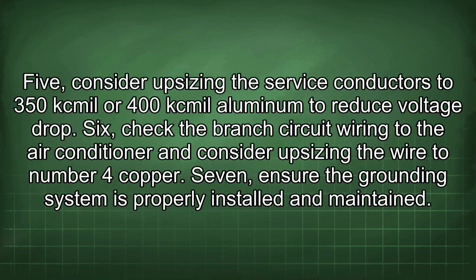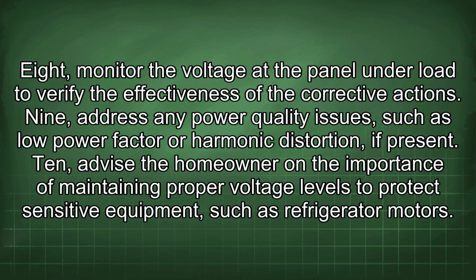5. Consider upsizing the service conductors to 350 kcmil or 400 kcmil aluminum to reduce voltage drop. 6. Check the branch circuit wiring to the air conditioner and consider upsizing the wire to number 4 copper. 7. Ensure the grounding system is properly installed and maintained. 8. Monitor the voltage of the panel under load to verify the effectiveness of the corrective actions. 9. Address any power quality issues, such as low power factor or harmonic distortion, if present.